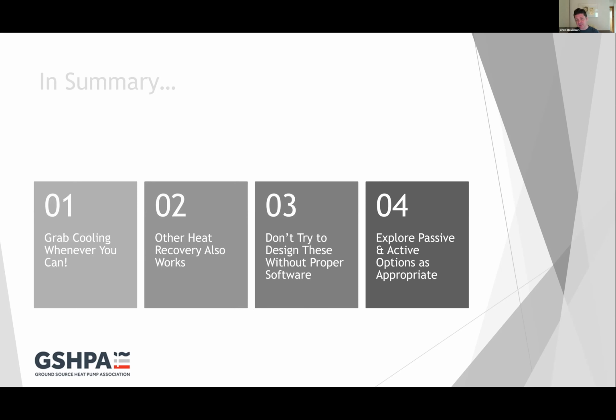Do not try and design one of these without proper software. The MCS tables are not equipped to design any cooling systems on any systems of any size. So please use a professional to run a proper piece of software through to design them. And then finally, explore your passive and active options. Are there opportunities to maybe manage that cooling load down a little bit and go to a passive option? Or actually, do we have to go to an active cooling mode?